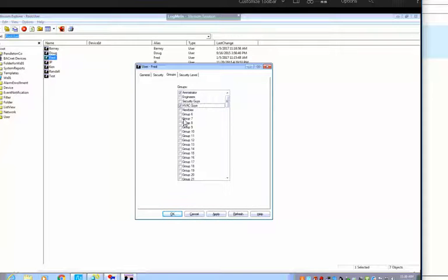And if you have all those groups selected that he should do, like I say, you could have multiple groups in there. Administrator kind of takes over all those functions, allows him to do anything. So if you want to not allow him to do that, you have to uncheck the administrator, because it covers everything. But now he has the ability to do anything the engineers are allowed to do, anything the HVAC guys are allowed to do. And if he becomes your security guy, you can check that as well.